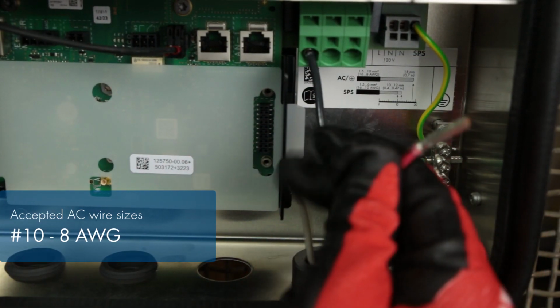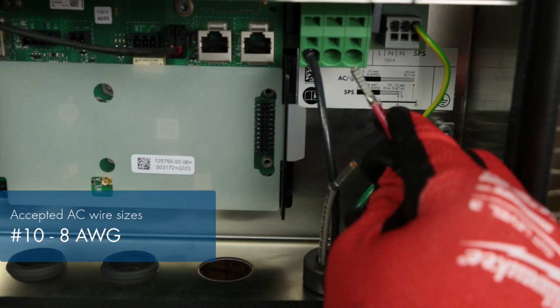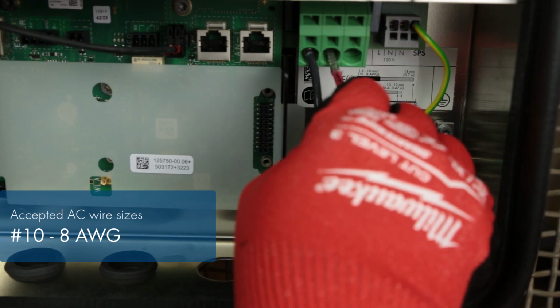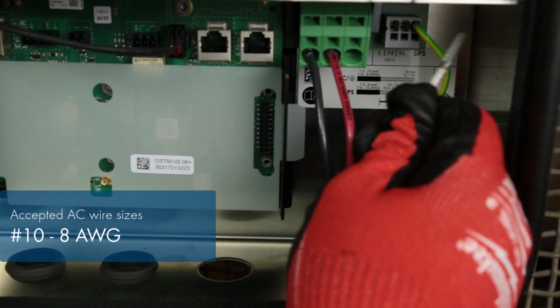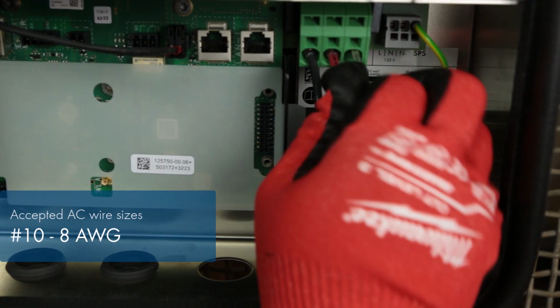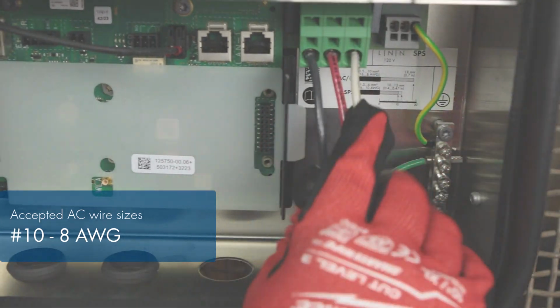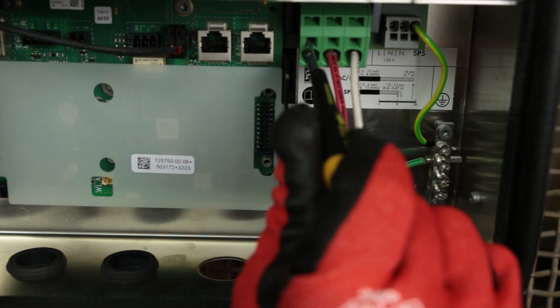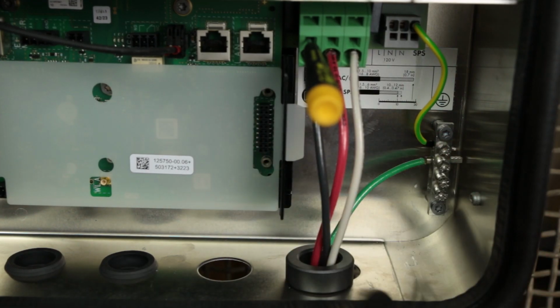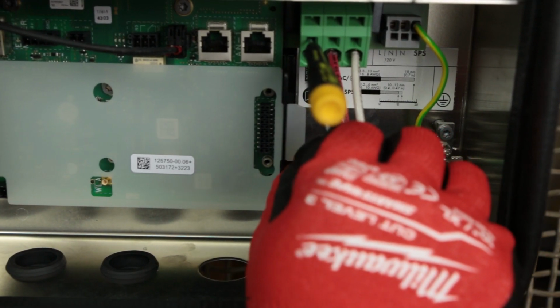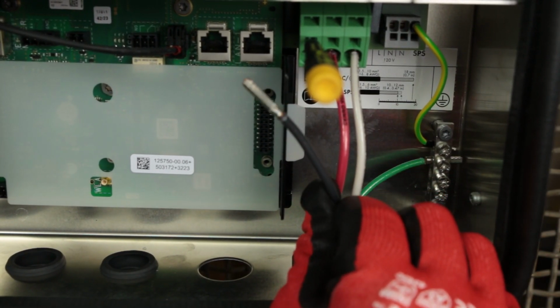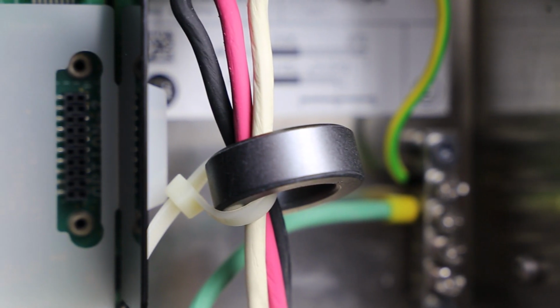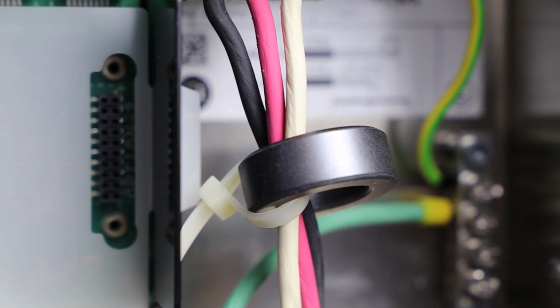For both solid wires and those equipped with ferrules, you can directly insert your wires into the respective terminals without opening the clamps. To uninstall a wire, insert a small screwdriver here to open the clamp and gently pull out the wire. Use your zip tie to tie the conductors.